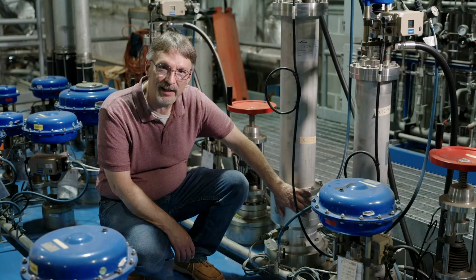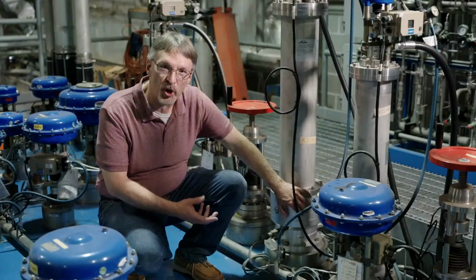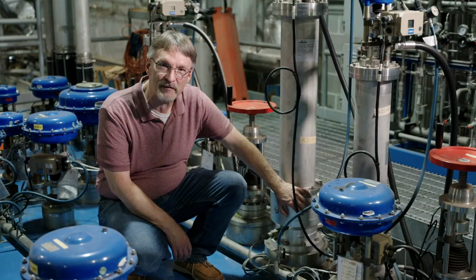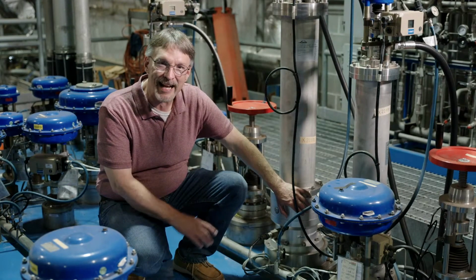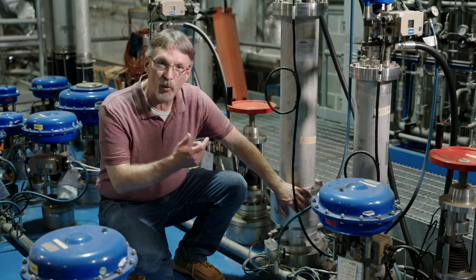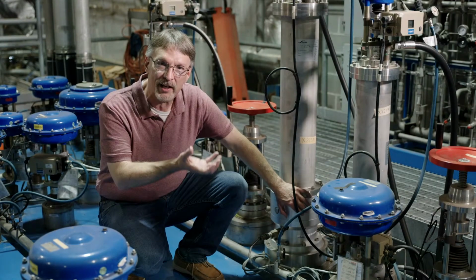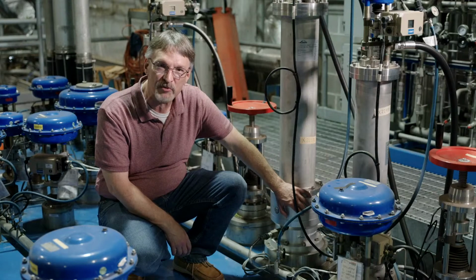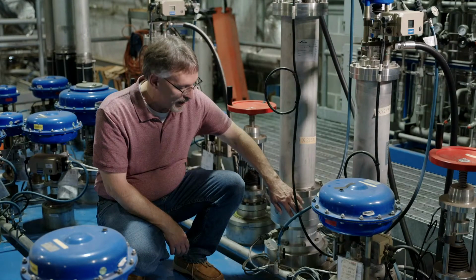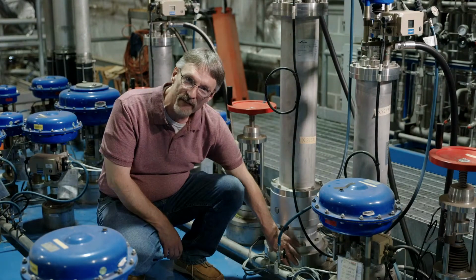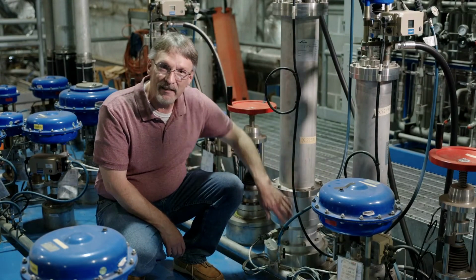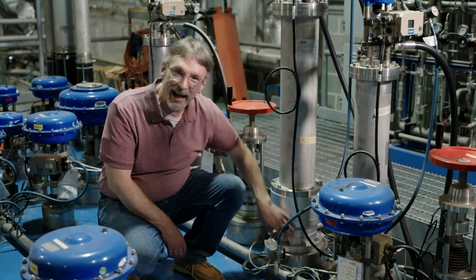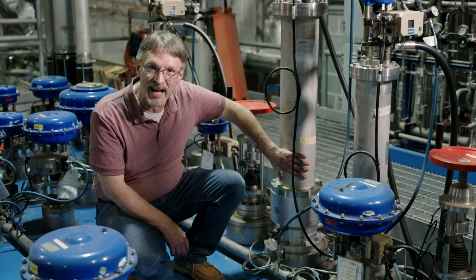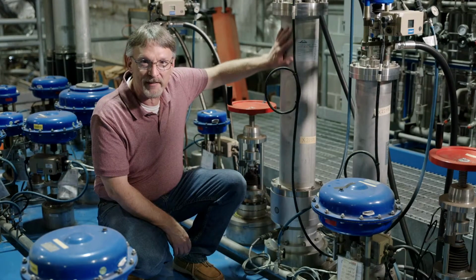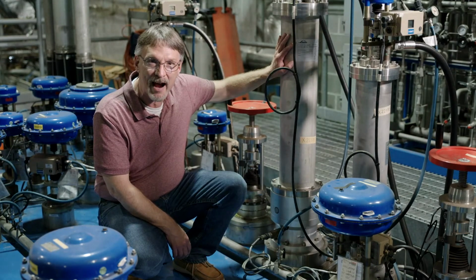It takes in the high pressure helium and forces the wheel to spin at speeds of up to 250,000 revolutions per minute. It has no mechanical bearings. It uses a gas stream around the shaft to hold it and allow it to spin at these incredible speeds. The energy basically gets transferred from this side of the turbine to this side. The gas on this side gets colder, and the gas on this side gets warmer, where it's cooled in this water jacket, which sends the energy out to our cooling towers.